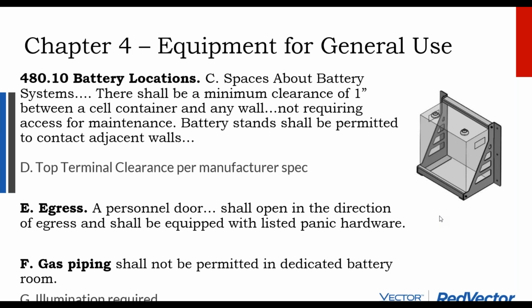And there needs to be a 1-inch clearance between the cell container and the wall. And so you'll see battery mounting brackets that will separate the wall from the battery when you are wall mounting your batteries. Or if you're floor mounting the batteries, you can't just butt them up against the wall. They're not permitted to contact that adjacent wall. Even the shelf itself will have this clearance requirement, and we'll reference that a little bit later. The terminal clearances, how much vertical space you need between the battery and the shelf above it, that is driven by the manufacturer spec. So that's not a clearly defined vertical clearance in code.